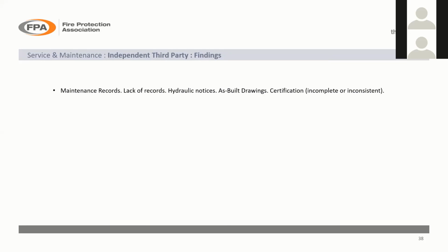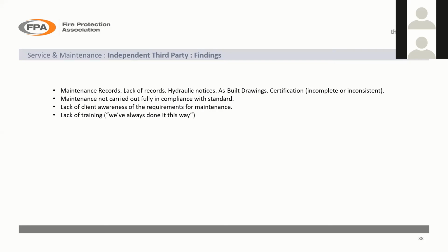It should be done. So the maintenance isn't fully carried out in compliance with the standard. So, for example, review of hazard isn't carried out. That's one of the common things that we see. But sometimes not all the testing regimes are followed. Water supplies aren't tested regularly enough. That kind of thing. Quite often there is a lack of client awareness of the requirements for maintenance, and just generally a lack of client awareness of the sprinkler system. So in places like shopping centres, a lot of the shopping staff, for example, have no idea what the sprinklers are. They think the fire alarm system is exactly the same as the sprinkler system, and there are big differences between the two.